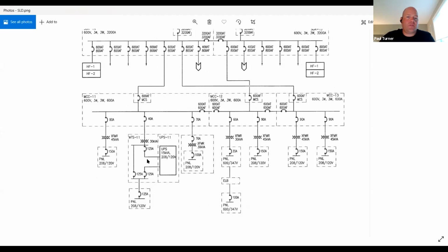Should that 600 volt feed disappear due to disruption to the utility power, the UPS can continue powering particular panel boards, ones that would be considered essential loads, for a period of time, not indefinitely, but depending on the battery capacity, for a duration of time, to continue powering those essential loads.